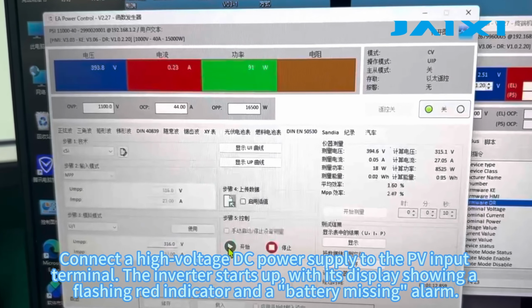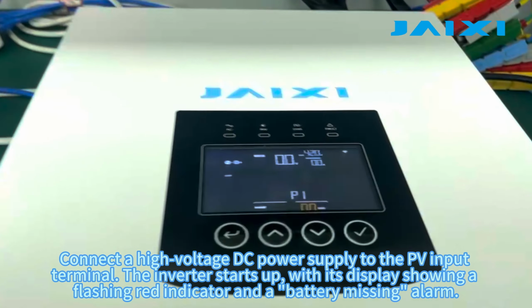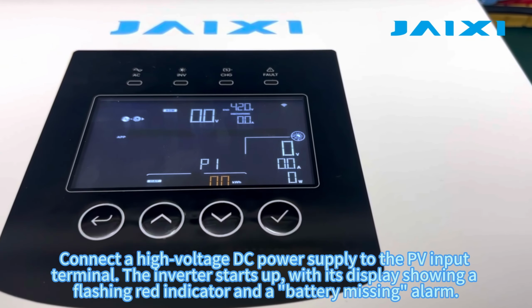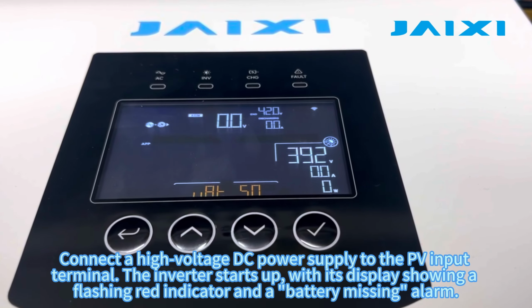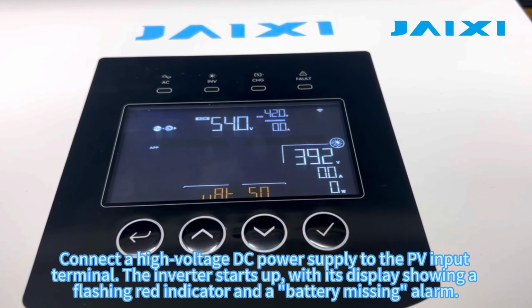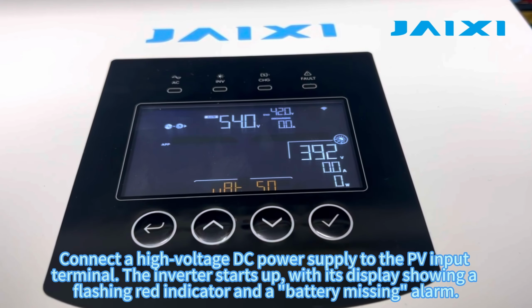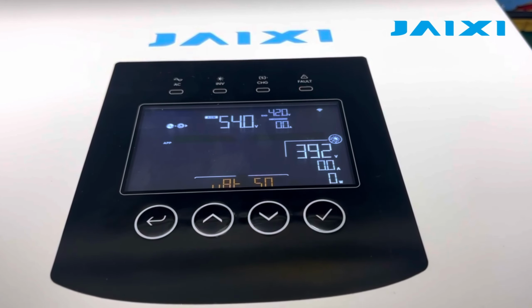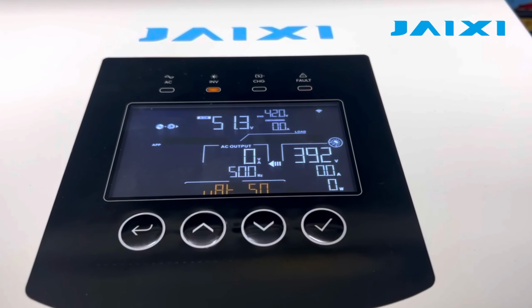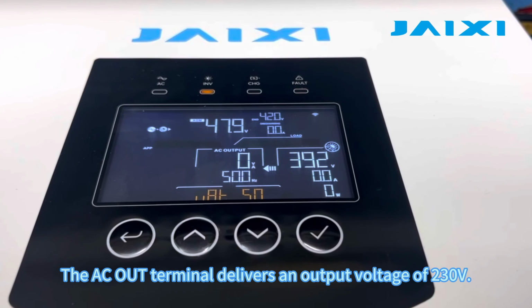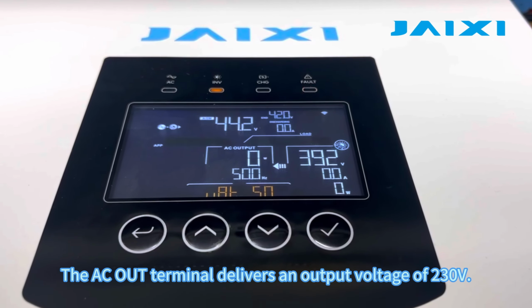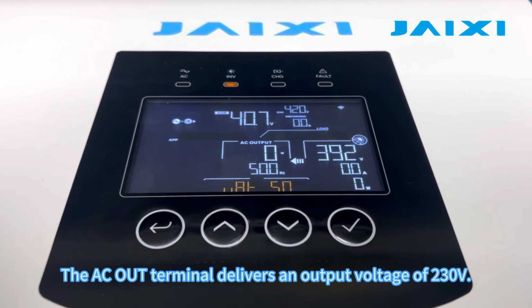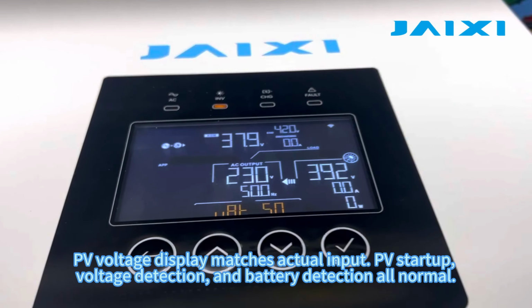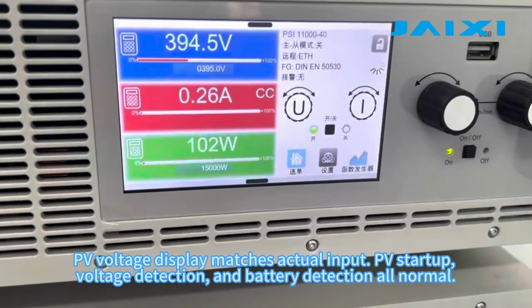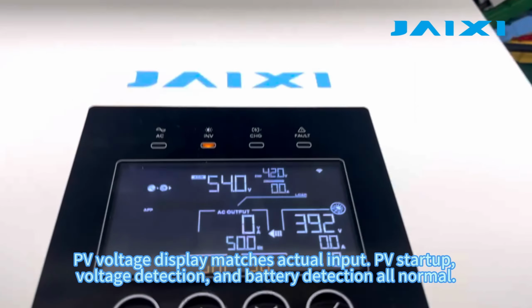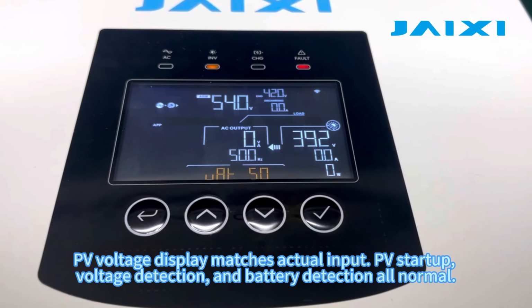Connect a high-voltage DC power supply to the PV input terminal. The inverter starts up, with its display showing a flashing red indicator and a battery missing alarm. The AC out terminal delivers an output voltage of 230 volts. PV voltage display matches actual input. PV startup, voltage detection, and battery detection, all normal.